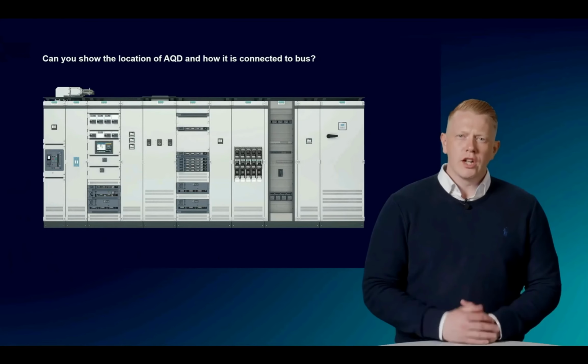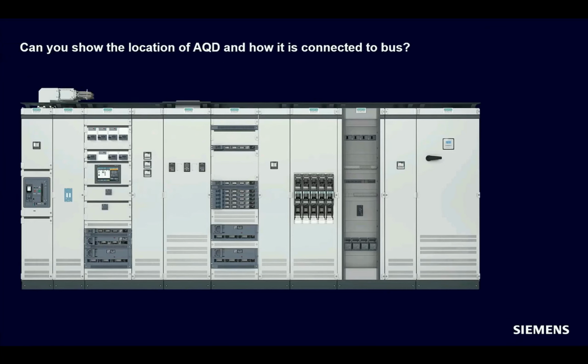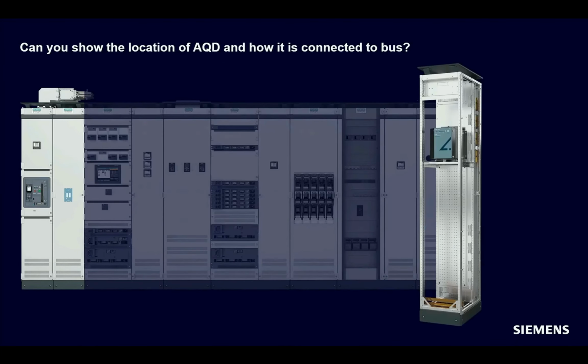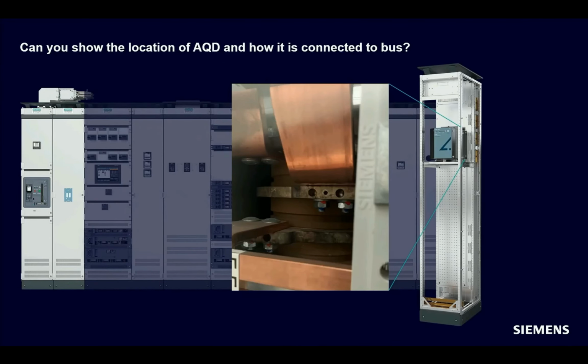Can you show the location of the AQD and how it is connected to the bus? The AQD should always be mounted as close as possible to the incomer to reduce stress on the system if tripped. The device is directly connected to the main bus bar.